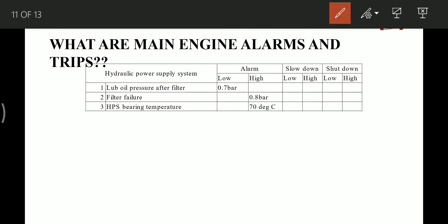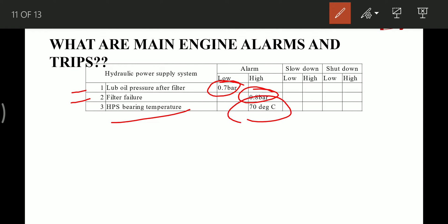Extra alarms are provided for ME engines (electronic engines). In the hydraulic power supply system: lube oil pressure after filter — alarm if less than 0.7 bar. Filter failure alarm if pressure is greater than 0.8 bar. HPS bearing temperature — alarm at 70°C or above. For all these alarms there is no slowdown or shutdown.